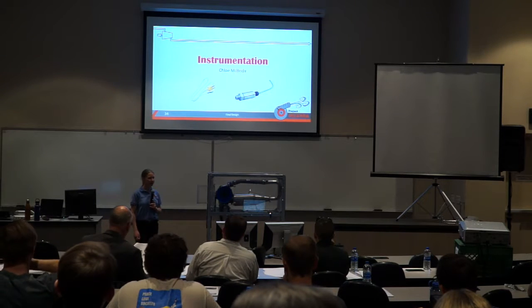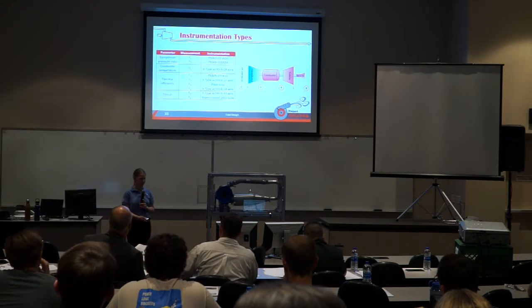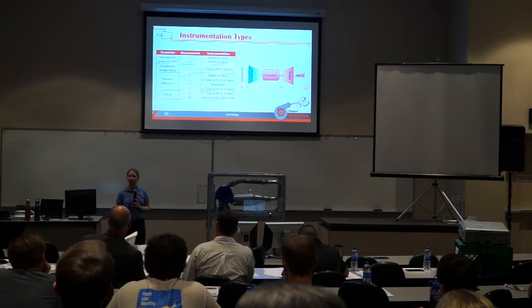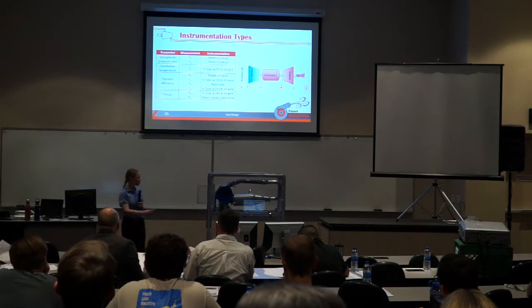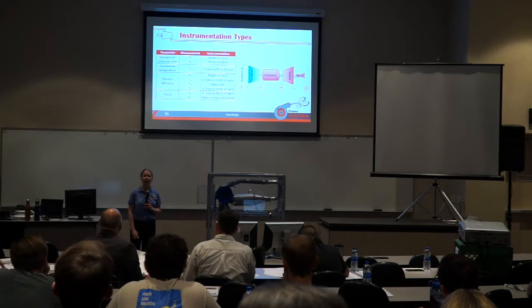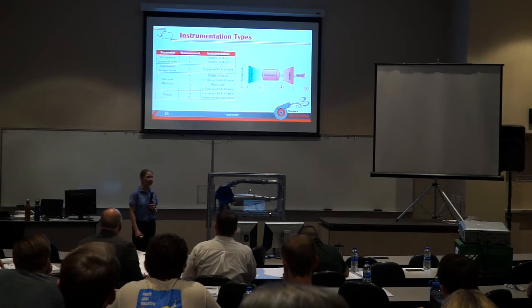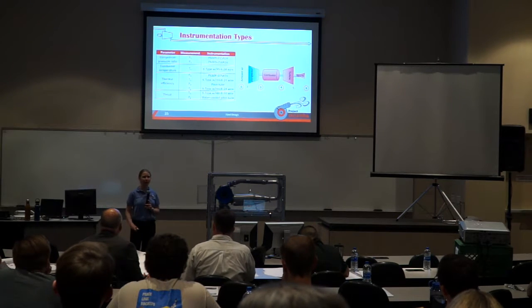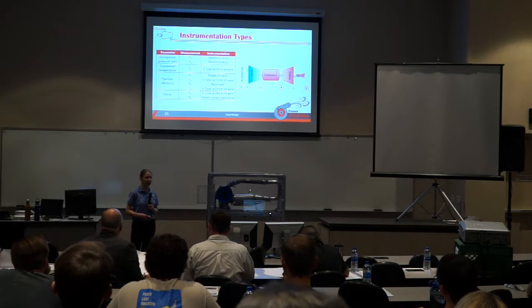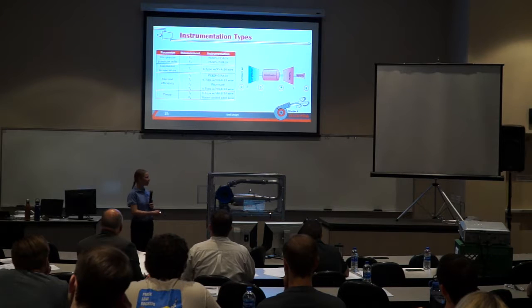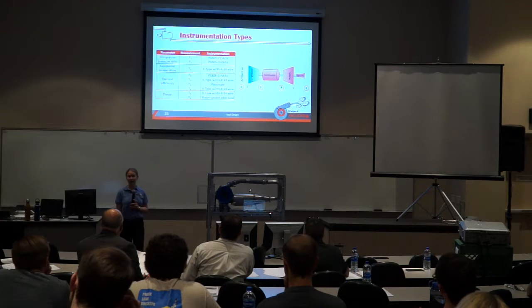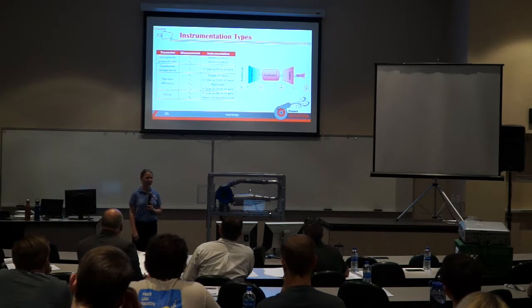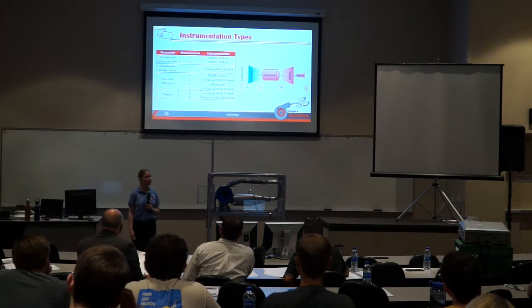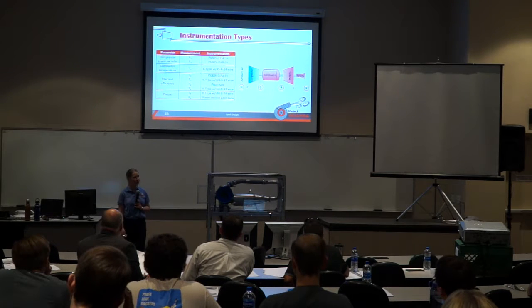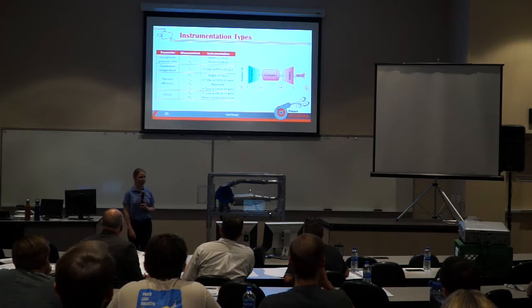And then a bit about instrumentation. We used mainly pressure transducers and thermocouples along with our pitot tube to try to get our temperatures and pressures. For the thermocouples, we used different types of insulation on the wires depending on what kind of temperatures they would be measuring. For our inlet, it was essentially measuring ambient temperature, somewhere between about 55 and 65 degrees, which was the outside temperature when we were testing. So we could use essentially any insulation on that.